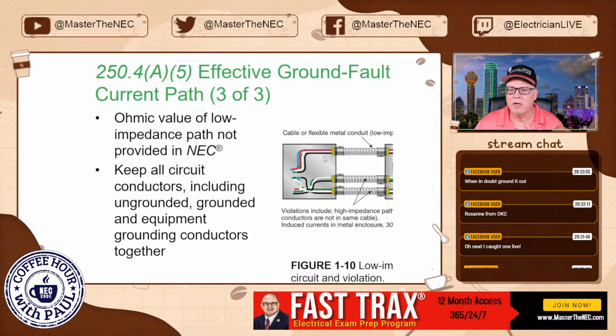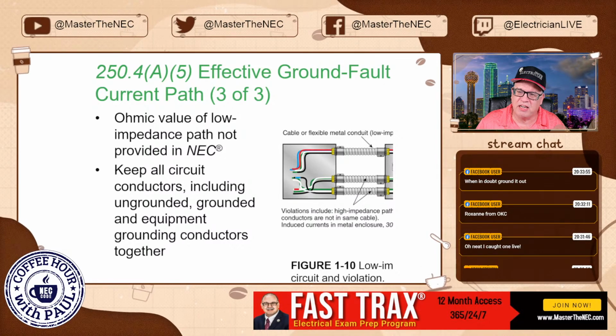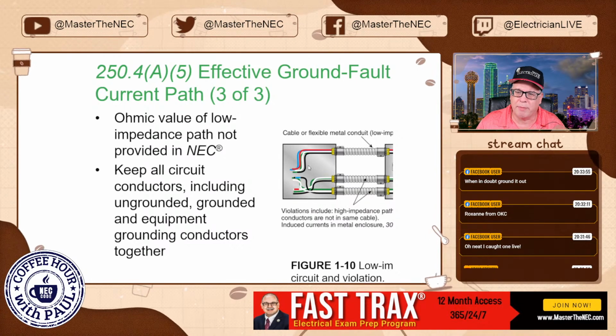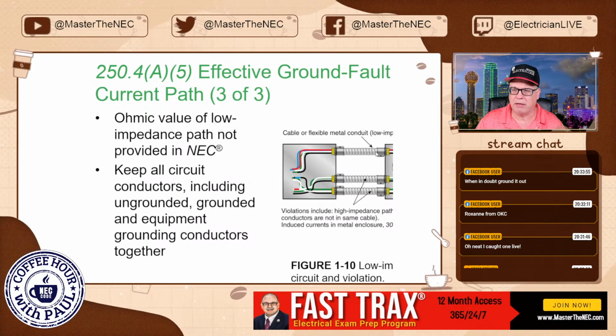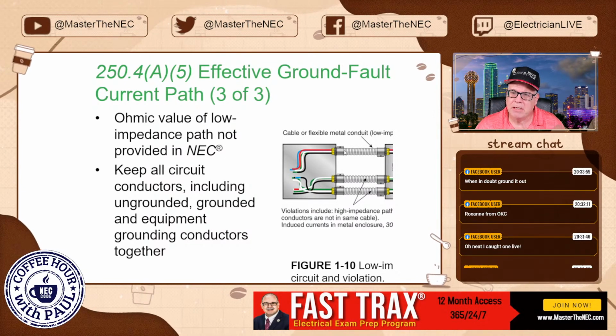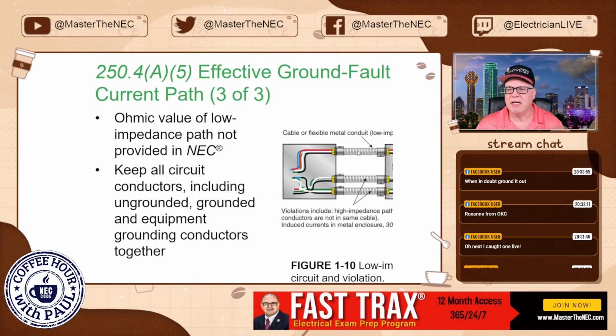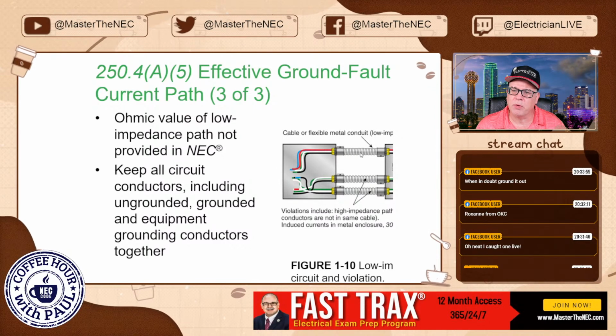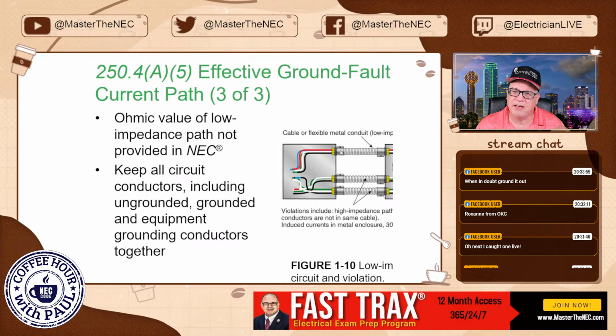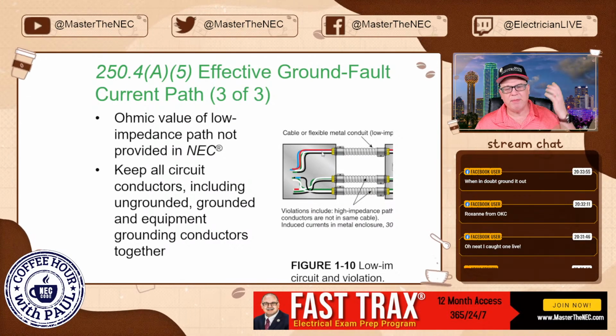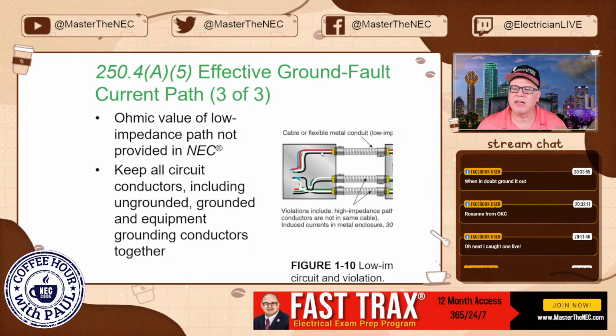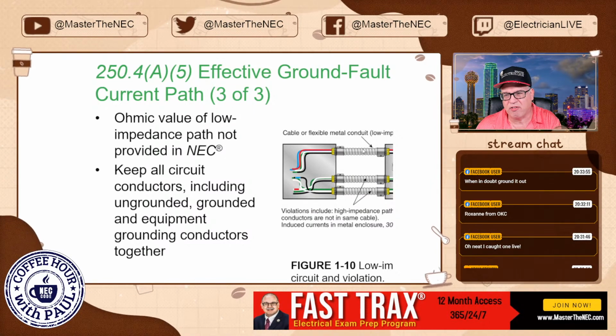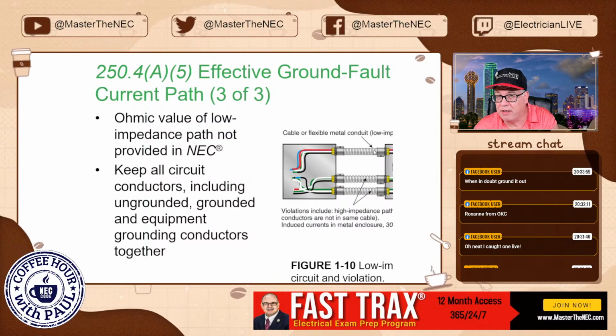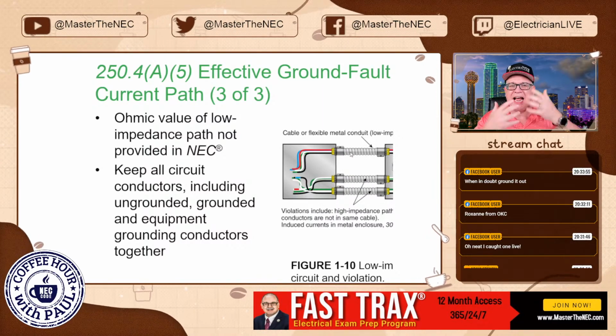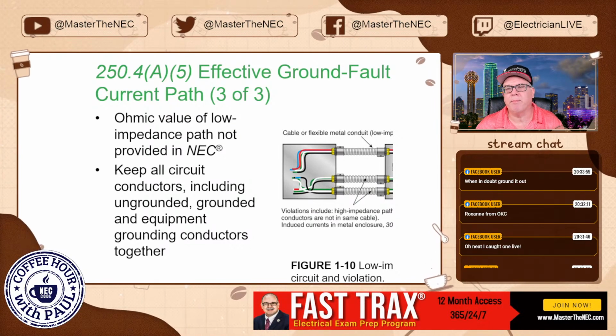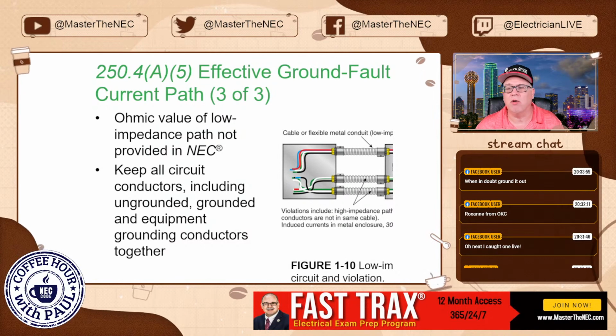Look at this example right here. So here you've got A, B, and C, let's say, and your grounded neutral conductor and your equipment ground all run through this flexible metal conduit. This is a low impedance path, okay? So you've got the equipment ground clear the overcurrent device. If the metal flexible conduit, FMC, gets energized, it's connected to a fitting. The fitting is connected to the metal cabinet. There's a good probability here, because of how this is all bonded, that it's going to clear an overcurrent device. Whether or not this qualifies as an equipment grounding conductor or not, there's still that bonding component in how you put things together. You have the greatest chance of clearing the overcurrent device, right?